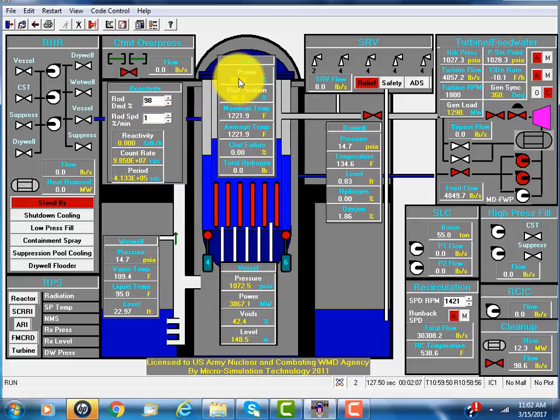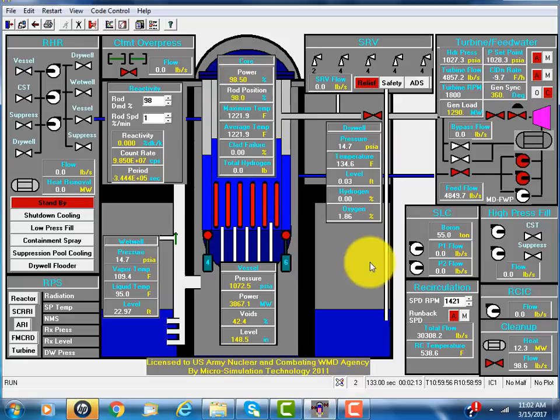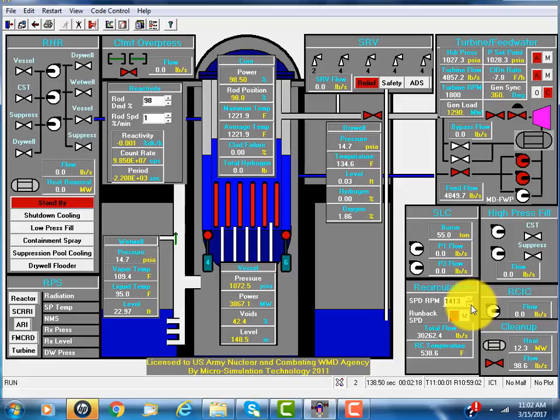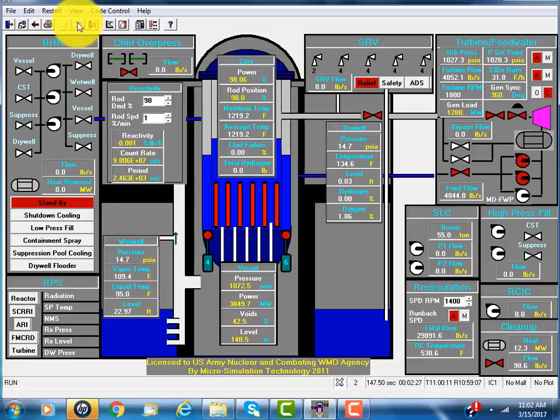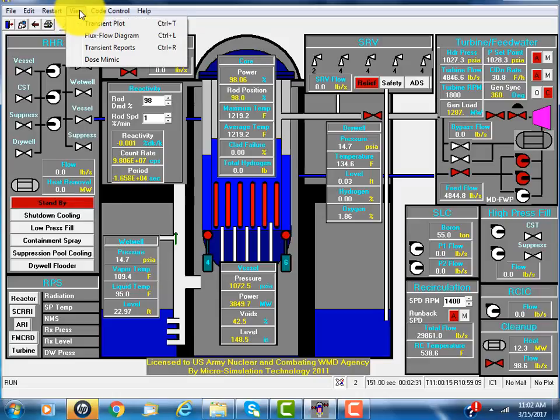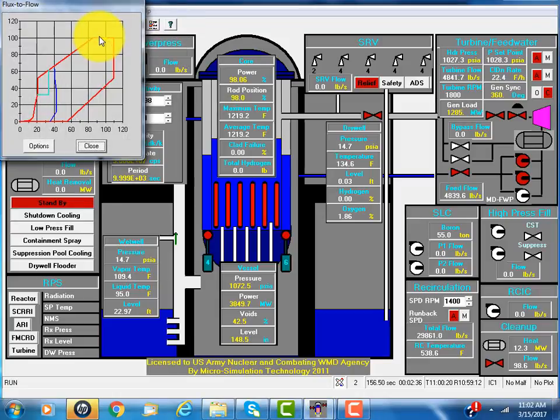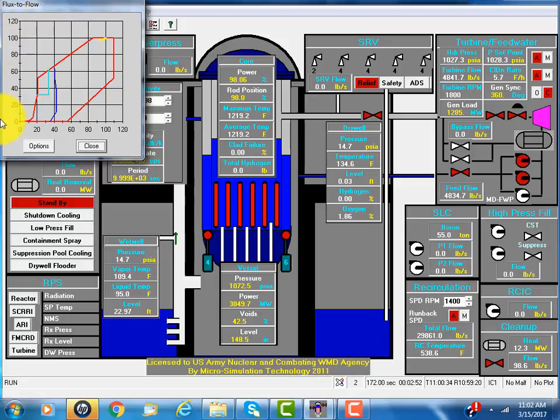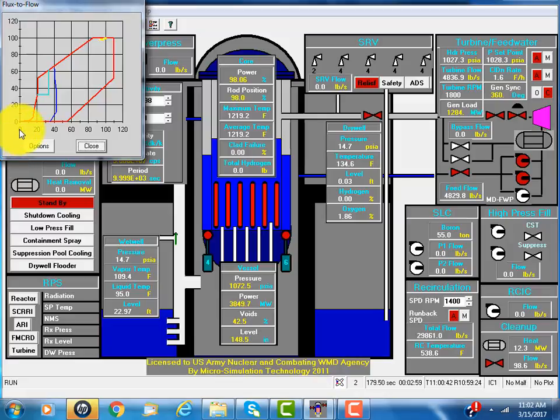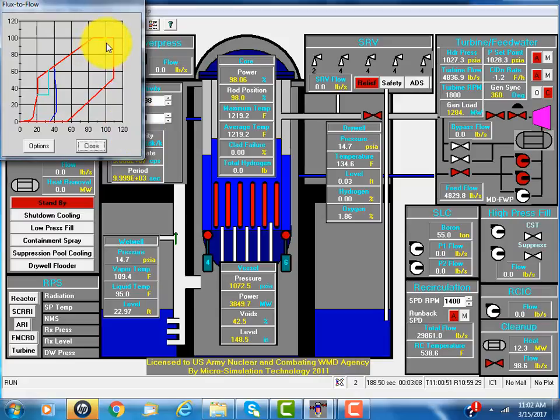Originally it's 100%, now power dropped to 98%. Suppose we reduce further, there's more reduction in power. We can view flux and flow map. The vertical axis is the flux, neutron flux, 0 to 120%. The horizontal axis is the flow, core flow. They're both 100% originally.